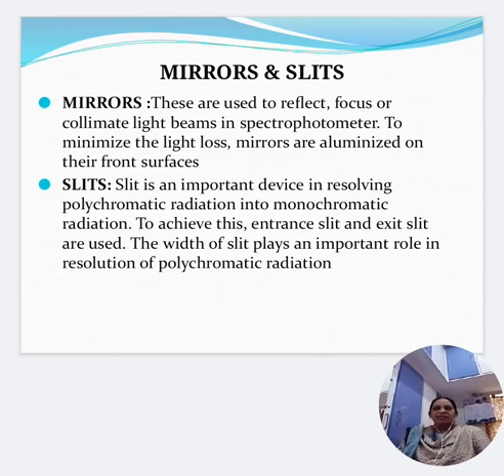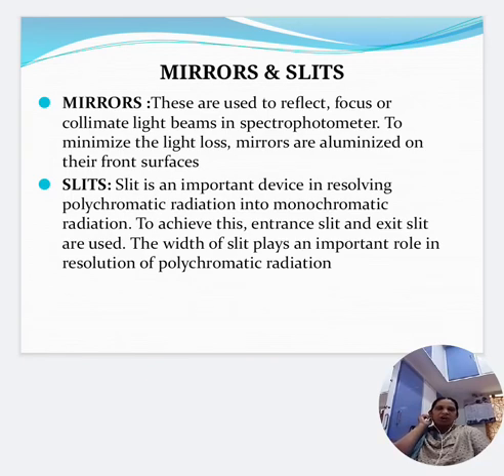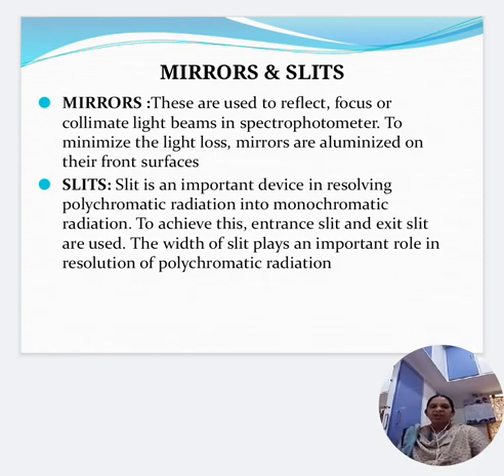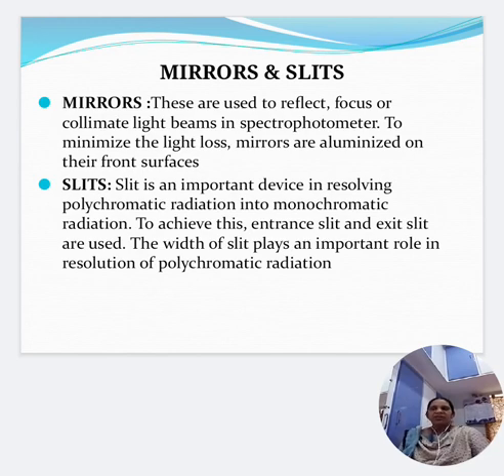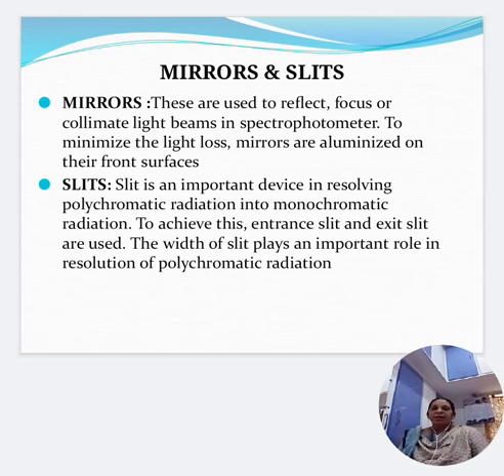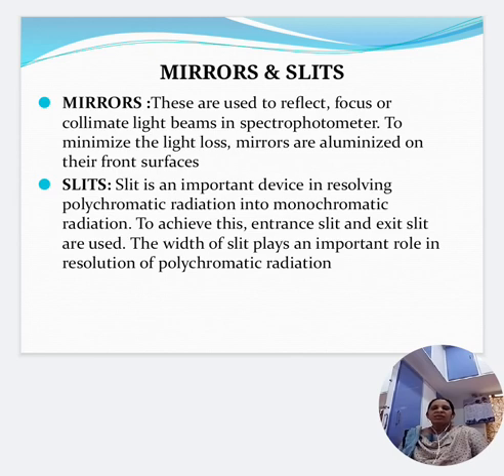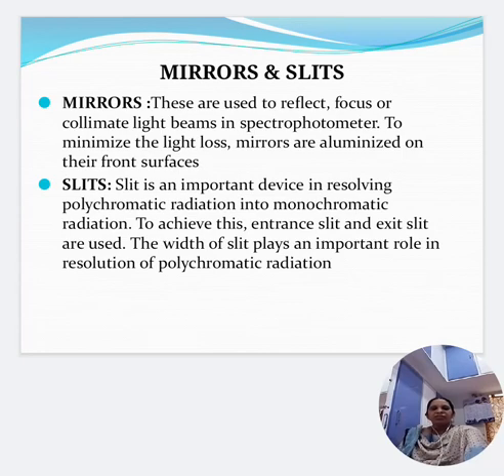Mirrors are used to reflect, focus, or collimate light beams in spectrophotometers. To minimize light loss, mirrors are aluminized on their front surfaces. Slits are an important device in resolving polychromatic radiation into monochromatic radiation. Entrance and exit slits are used, and the width of the slit plays a very important role in the resolution of polychromatic radiation.